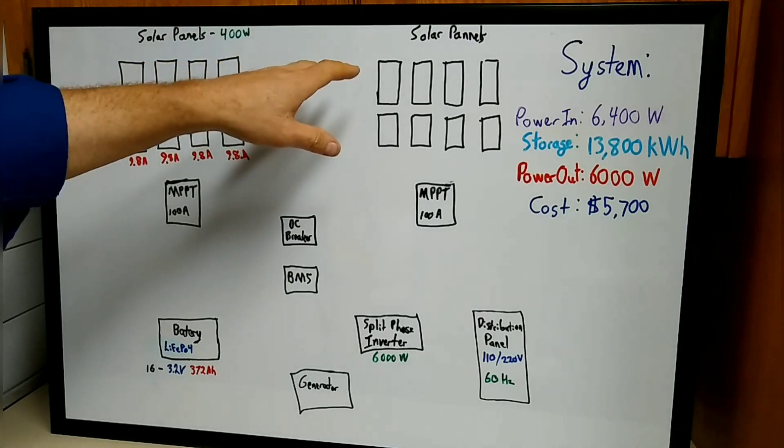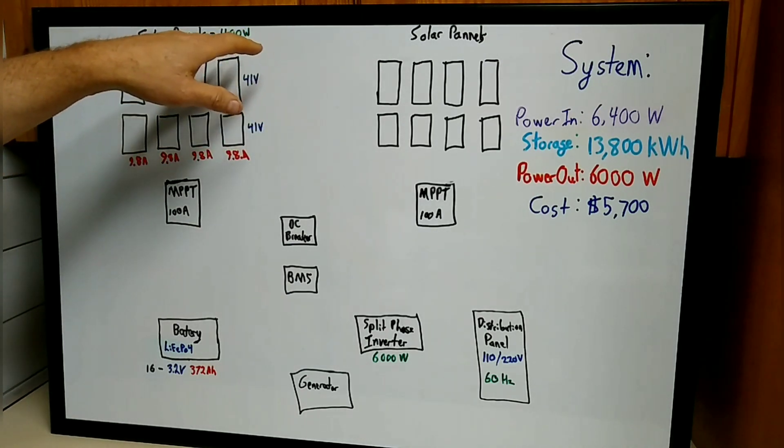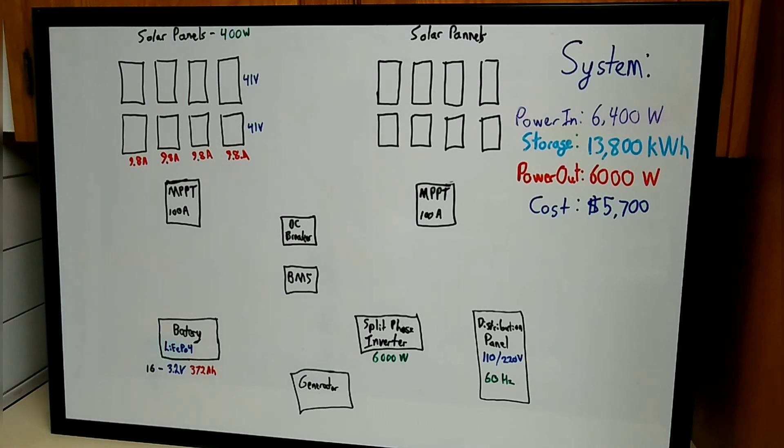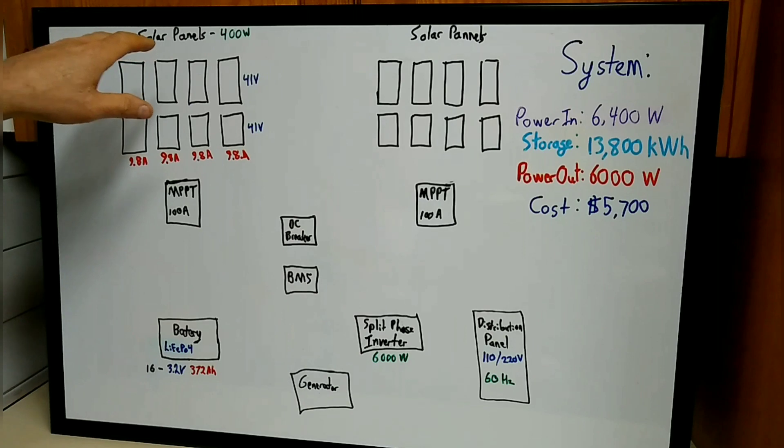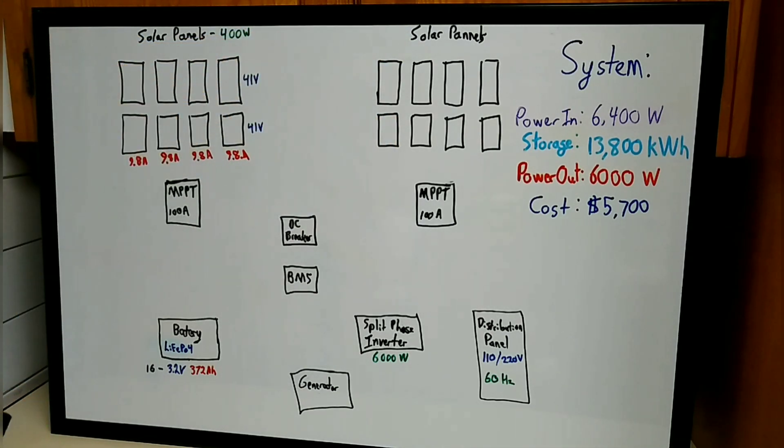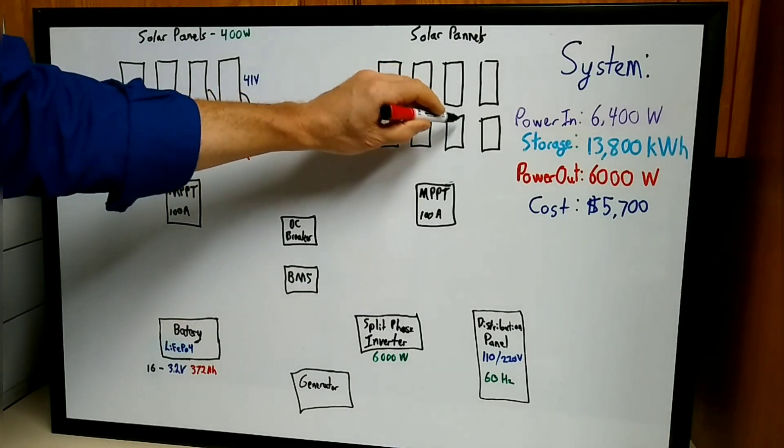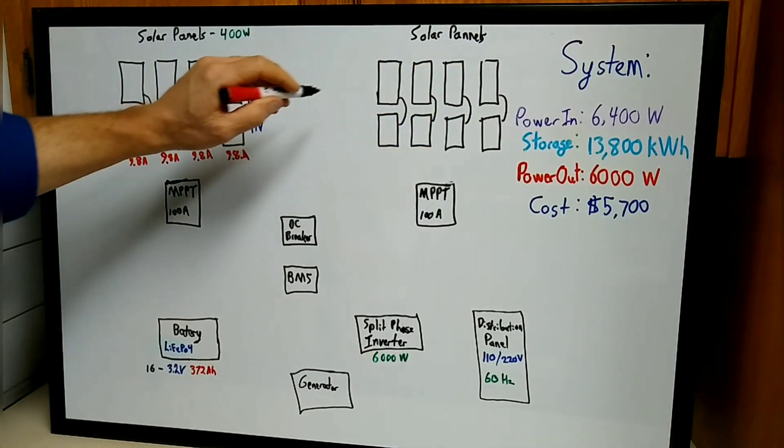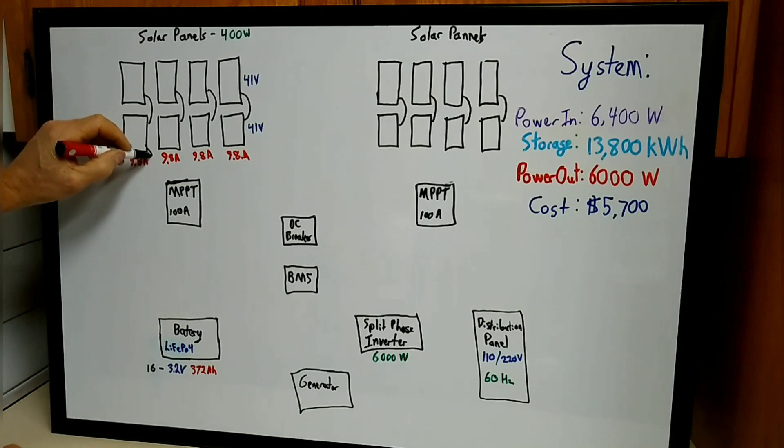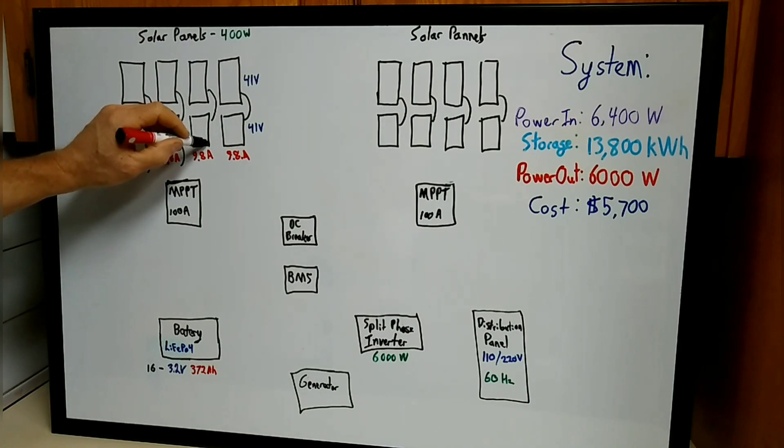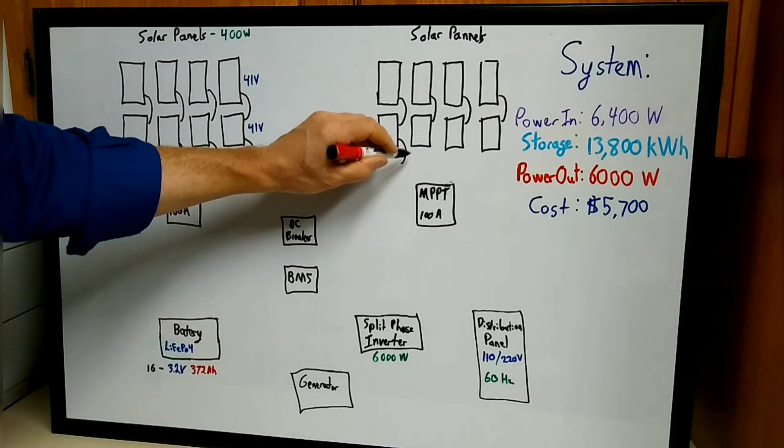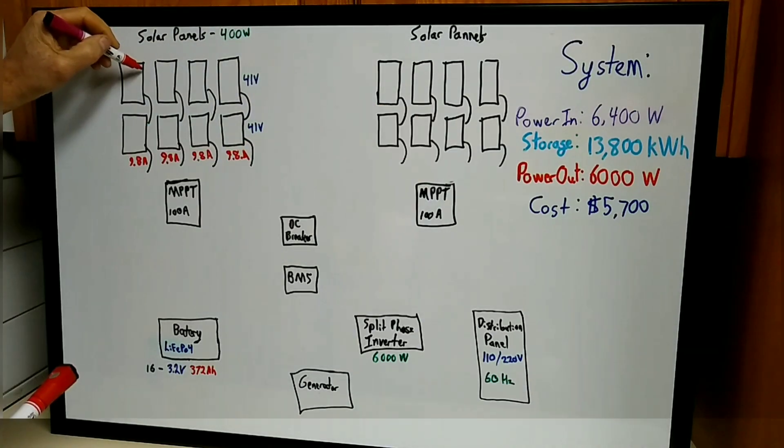So you multiply 400 by 16 to get 6,400 watts. That'll be the total watts coming into the house. I'm dividing those up into two arrays, two in series. In series means these two are connected like this. Each of the arrays will be two in series, four in parallel. I'm drawing out how they'll be wired together.